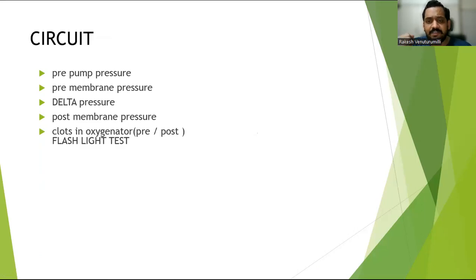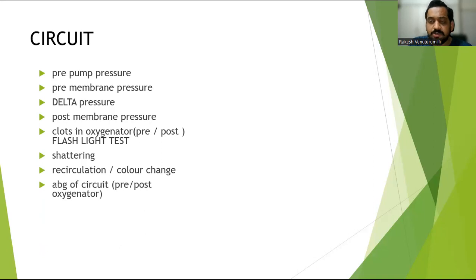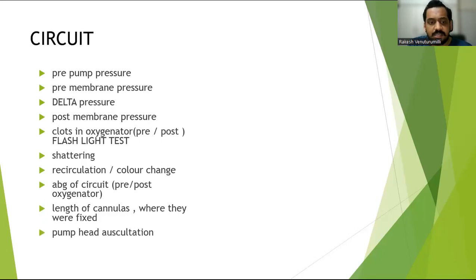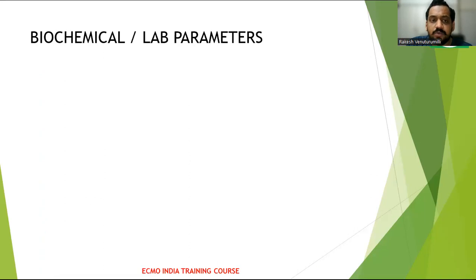Clots in the oxygenator: you need to do a flashlight test daily on your rounds, at least twice, I used to advocate, on both the pre- and post-membrane sides to find out the clots. And then tube chattering: you have to optimize the hemodynamics and volume status of the patient. Recirculation: identify the color change, and try to calculate the recirculation once in a while. Do an ABG of the circuit as and when required, and if you think the oxygenator is failing, you need to check the ABG of the circuit. Check the length of the cannulas where they have been fixed, so you need to check the cannula positioning. And then auscultation of the pump head is also very important. You can identify a clot sitting in the oxygenator as early as possible with a simple auscultation technique daily. So try to incorporate those things.